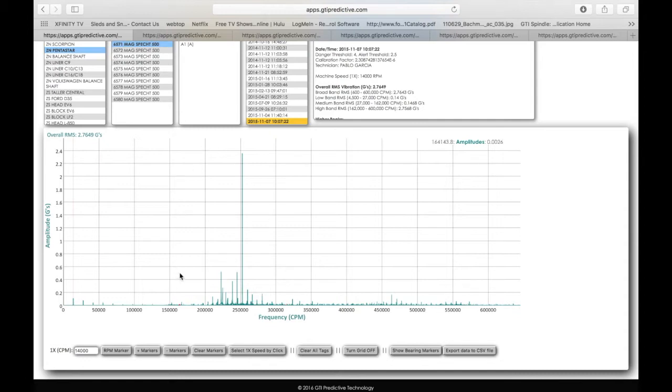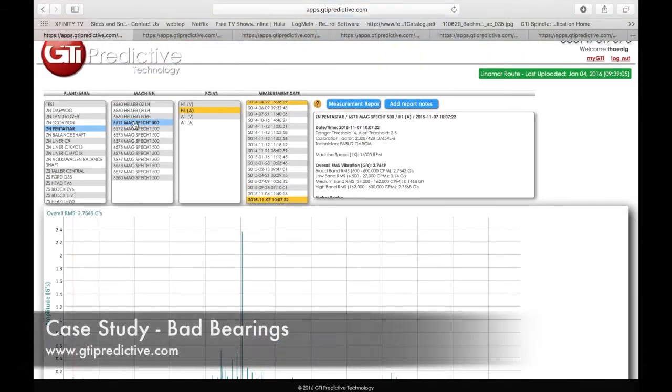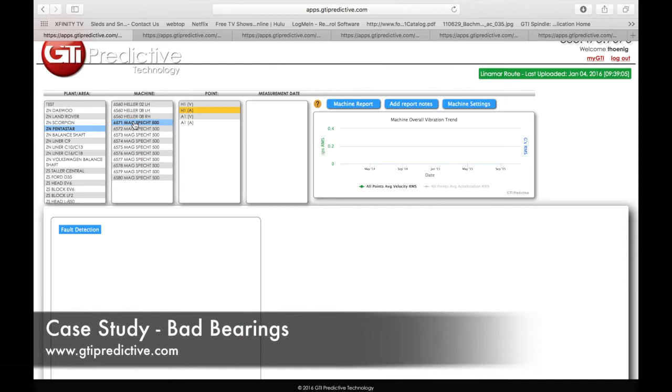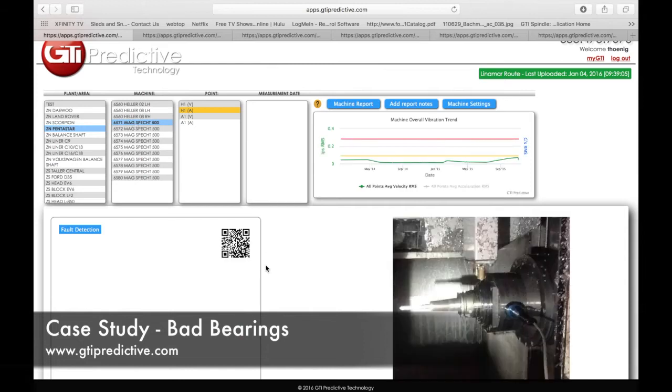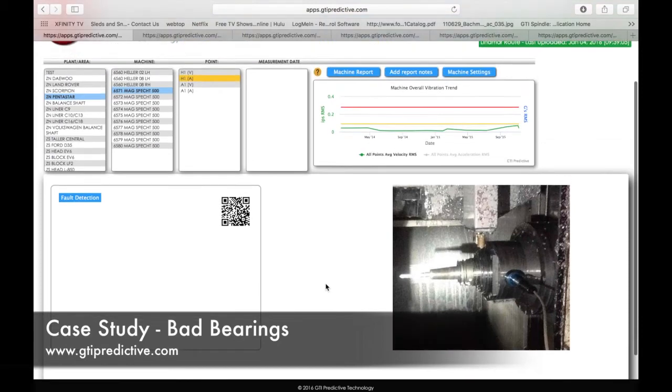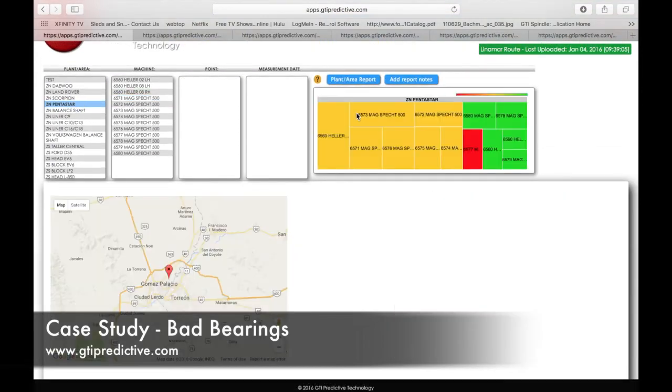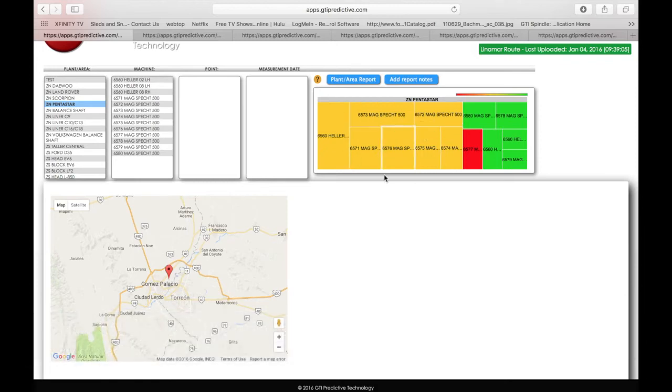Seeing our running speed over here and seeing that these bearing frequencies are elevated and heading in the wrong direction. So you can see again, this app can very quickly work with you and enable you to be able to find these faults and find these problem areas right away through this heat map.